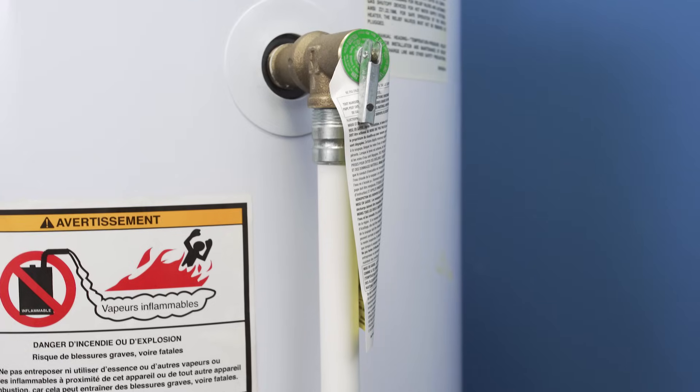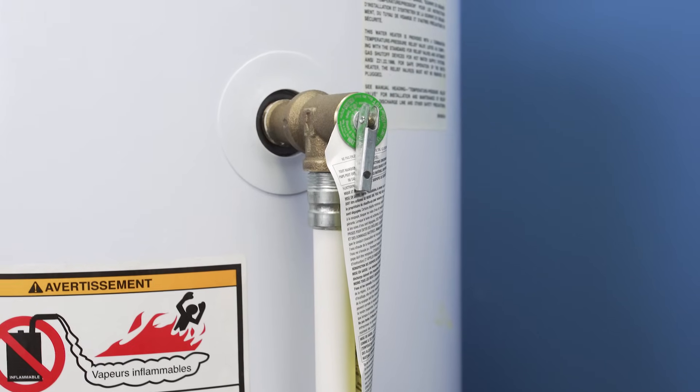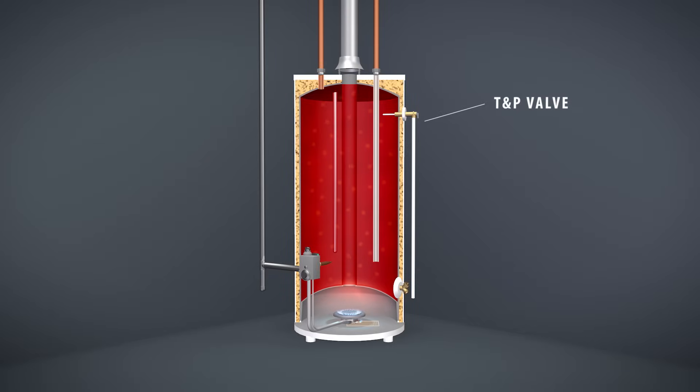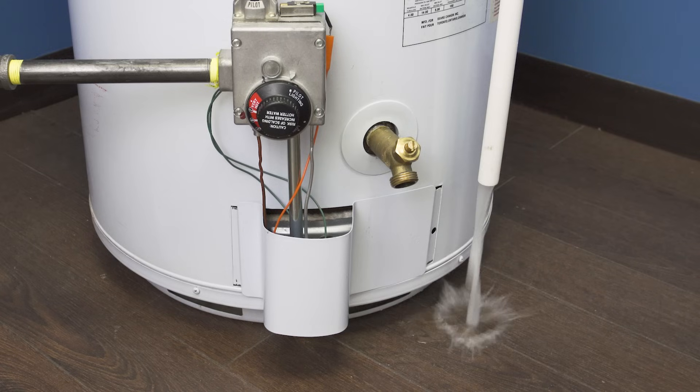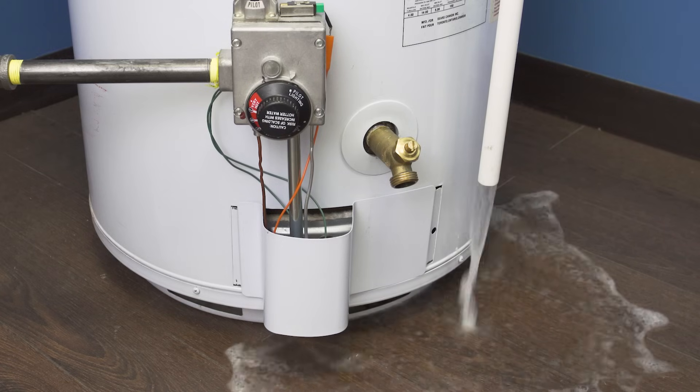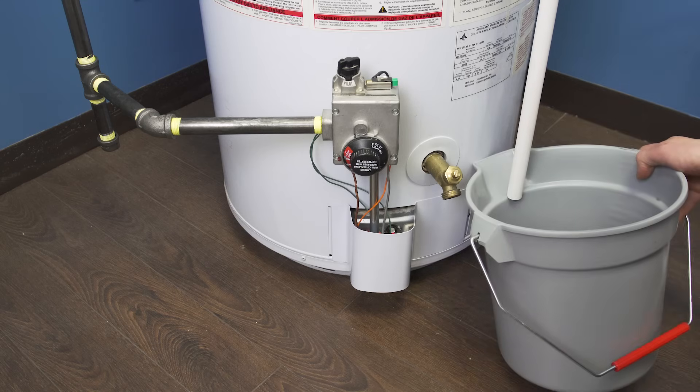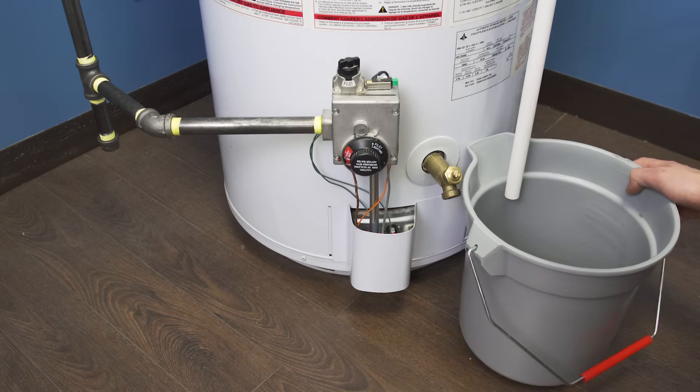The temperature and pressure relief valve is by far the most important safety device in water heaters. If the pressure or temperature inside the tank gets too high, the valve will open and release water, preventing the tank from exploding. It's important to test the valve to be sure it can open when needed.